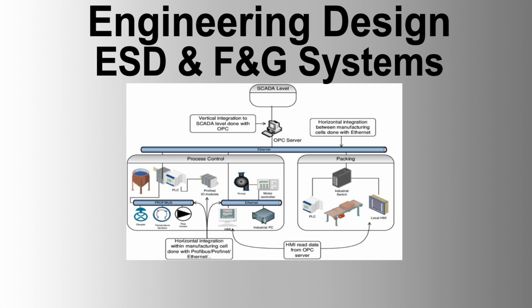Power supplies general requirements. 1. Redundancy. The ESD F&G system must include redundant power supplies to ensure continuous operation in case of a single power supply failure. Each power supply must be capable of supporting the full load of the ESD F&G system independently. 2. Capacity. The power supplies must be sized to handle the maximum load, considering all connected devices and future expansions. Power supplies should provide stable and reliable power to all system components.